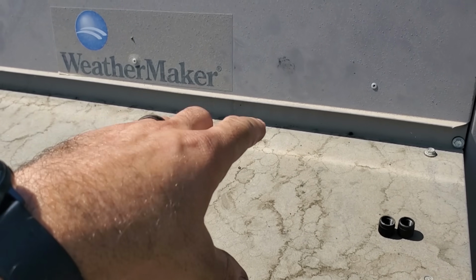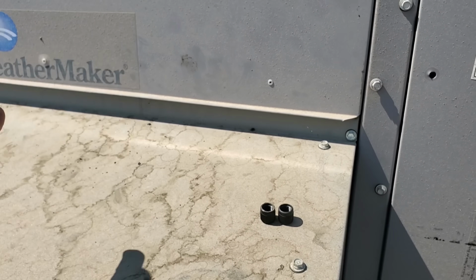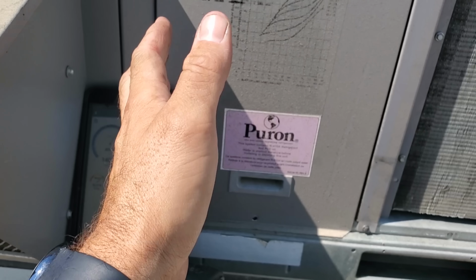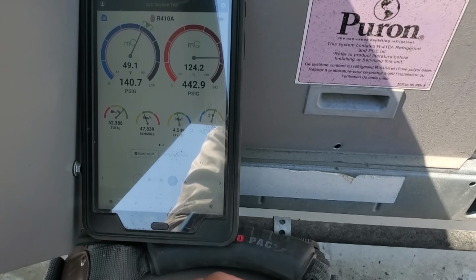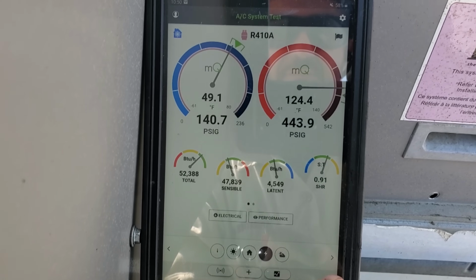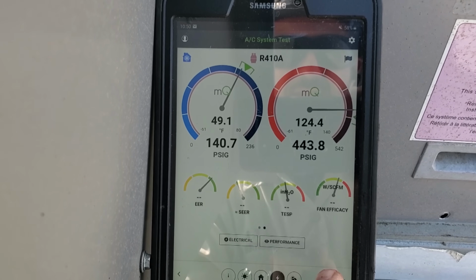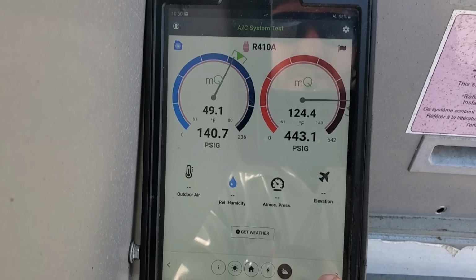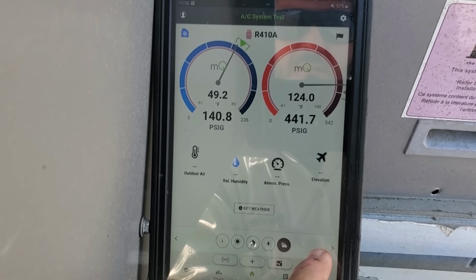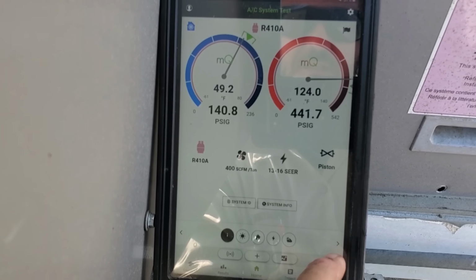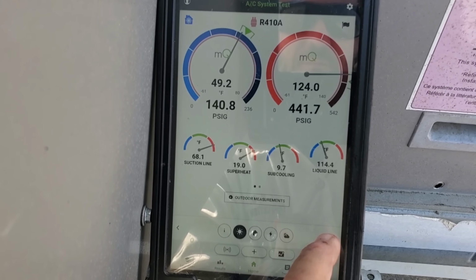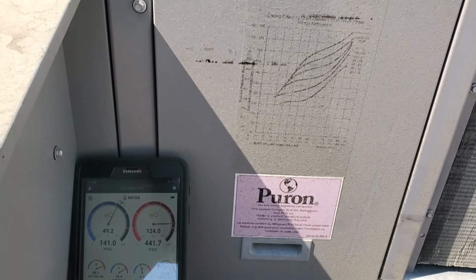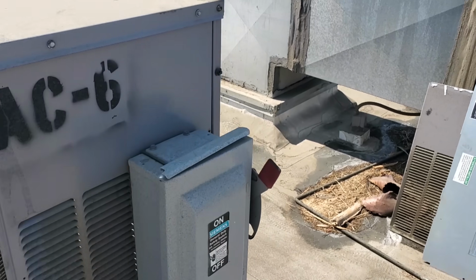Also on this unit, I noticed when I was pulling everything apart that the supply and returns aren't 100% open, meaning that it should have had a curb adapter basically. But these restaurants half the time don't want that stuff. They don't want to spend a bunch of money on all this. They just want cold, and they usually don't want to fix ductwork and things like that. I'm not scared about anything. Now, everything's kind of doing about as good as it can on this unit.